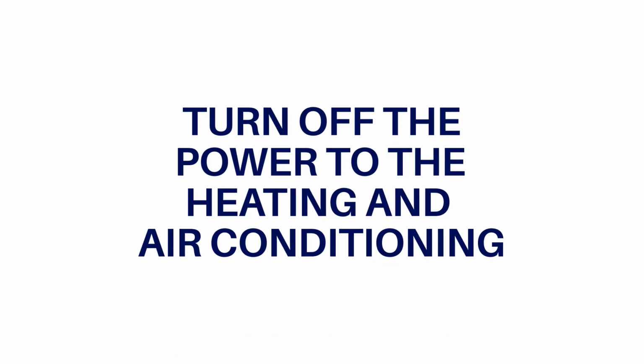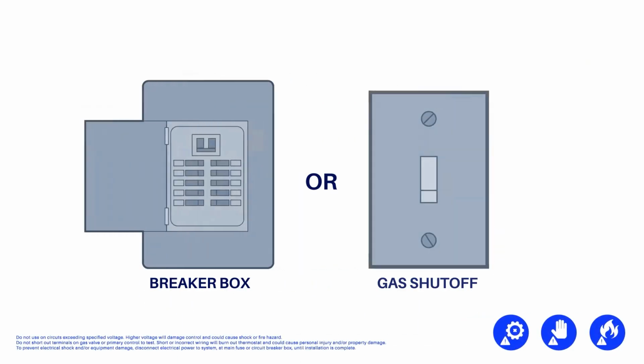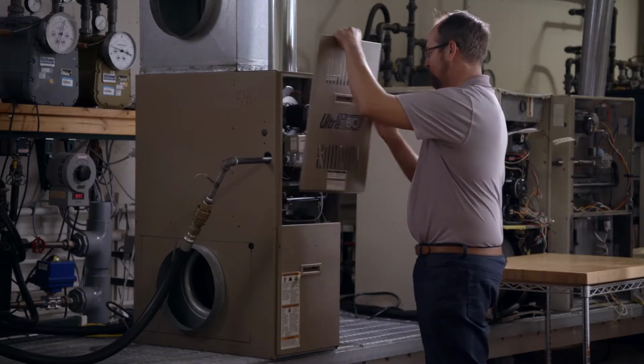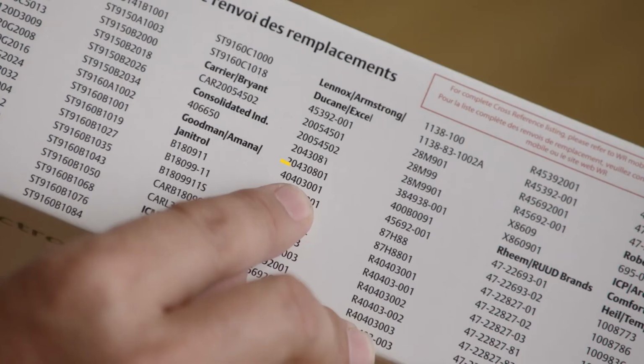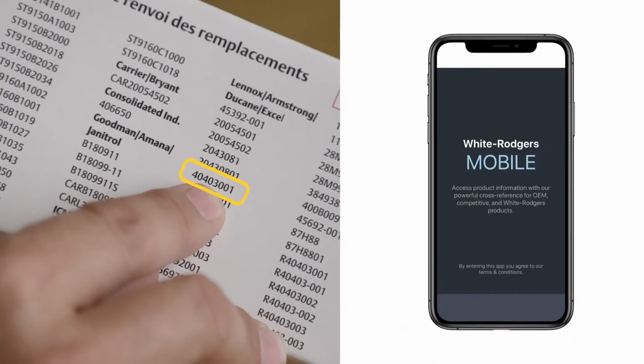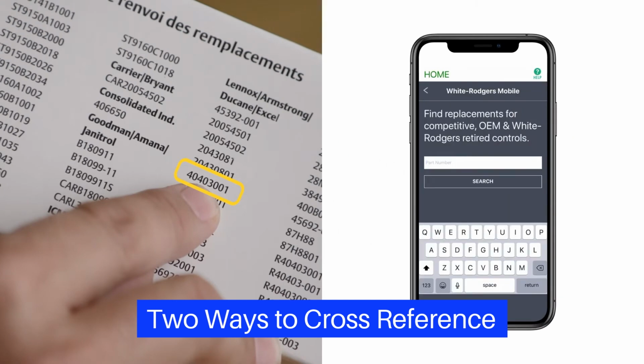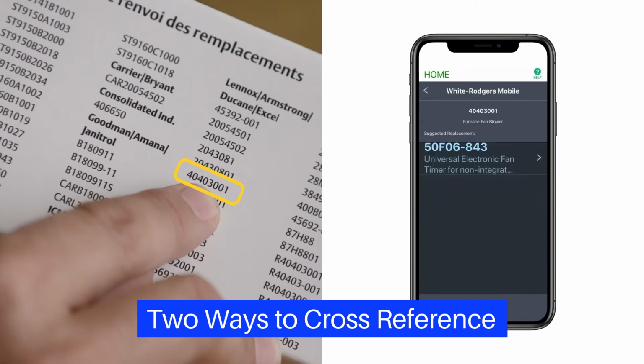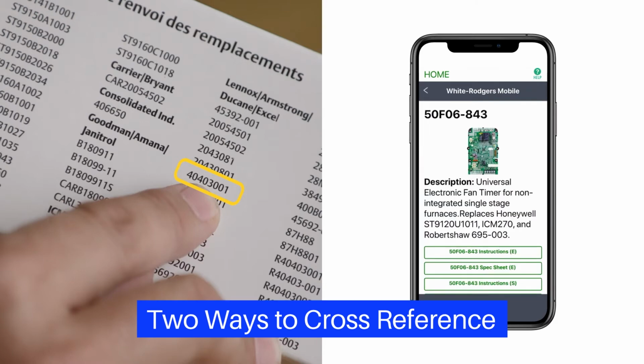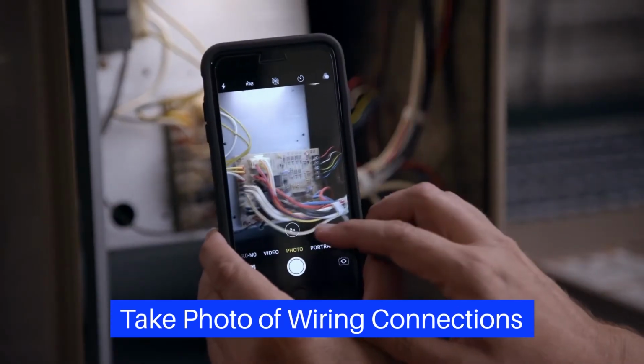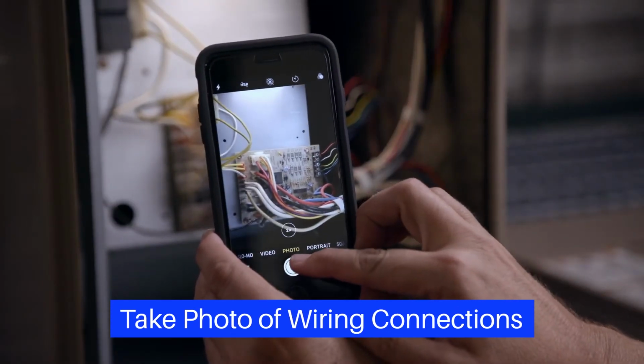First, ensure power and gas are disconnected prior to servicing the furnace. Remove the unit access panels. Check the part number on the existing control and verify it can be replaced with a 50F06843 using the cross references on the side of the carton or the White-Rodgers mobile app. Take a picture of the existing control for reference before disconnecting wires.